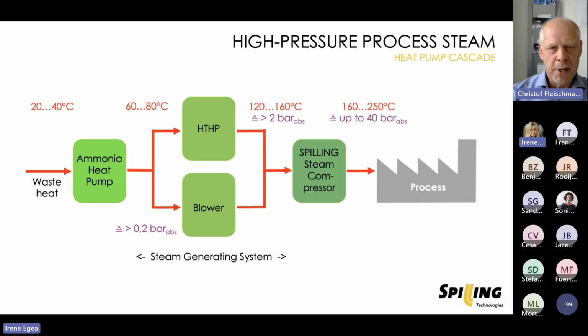The applications where heat sources with 60-80 degrees Celsius are available, and only the high temperature heat pump or the blower constellation has to be combined with Spilling steam compressors or with other mechanical vapor recompressors. These are more often found. So there are a lot of projects now in the feasibility stage or even in a more detailed engineering stage.